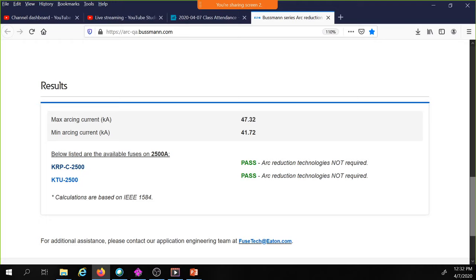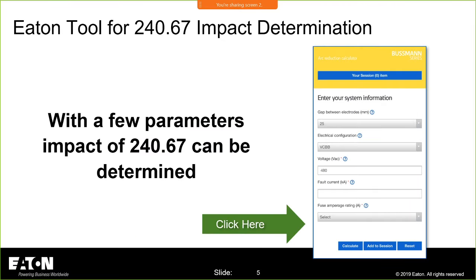Now, you'll say, Tom, why are you calculating two values of arcing current? That doesn't make sense. The code doesn't say which of these arcing currents, so why are you calculating two? IEEE 1584 calculates two values of arcing currents. One of the main reasons is that the equations we use in 1584 were developed in a lab, and we do tests over and over and over. And Dr. Lee down in Texas takes all that data back and graphs it, and then creates an equation to do curve fitting. And they calculate the minimum and maximums, because if you think about all these data points that you would have in your system.